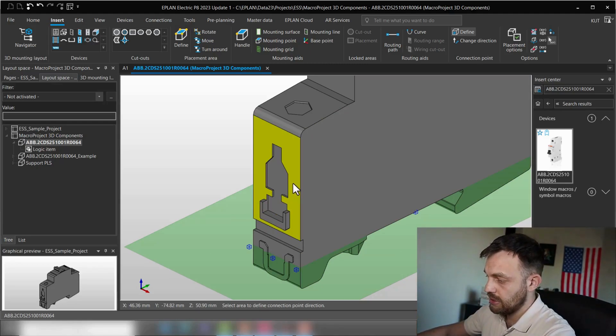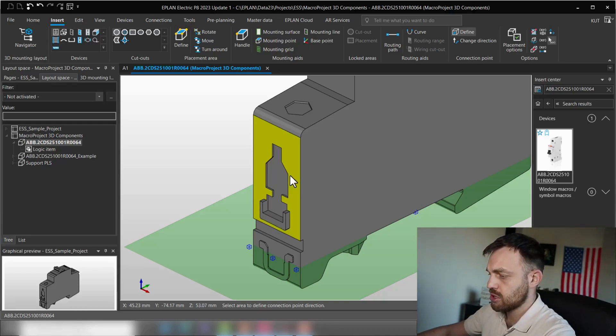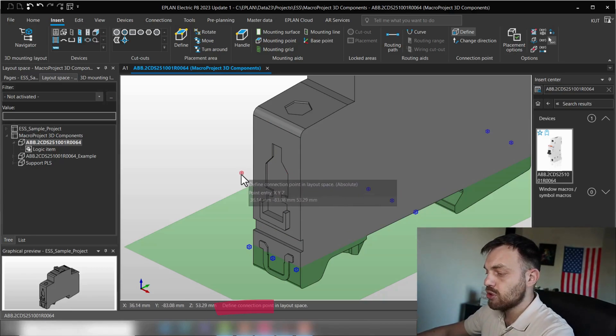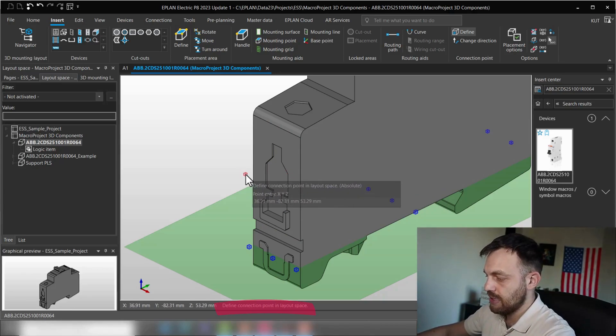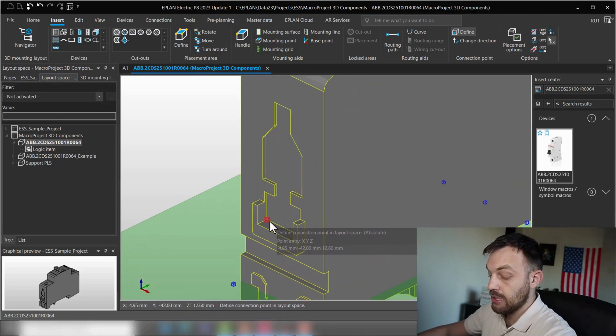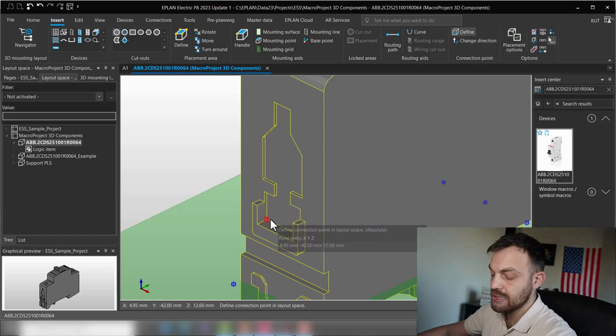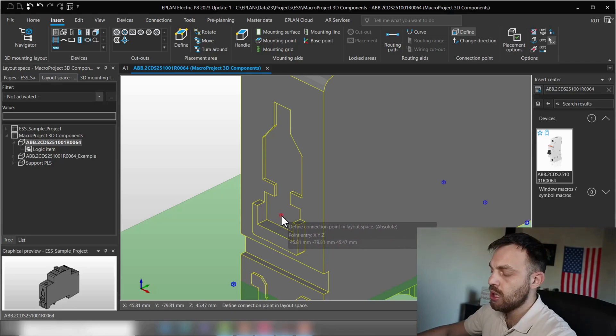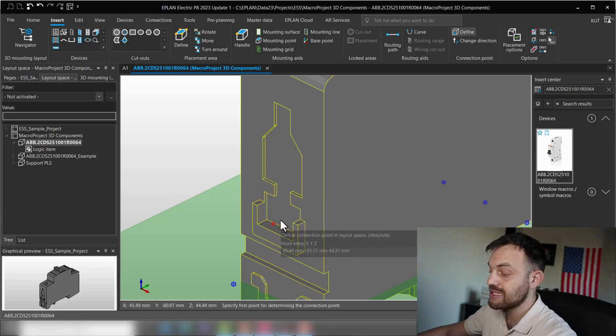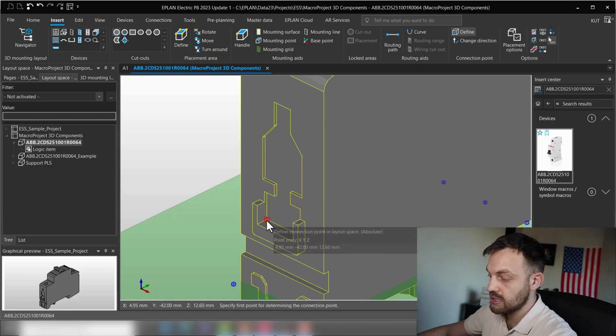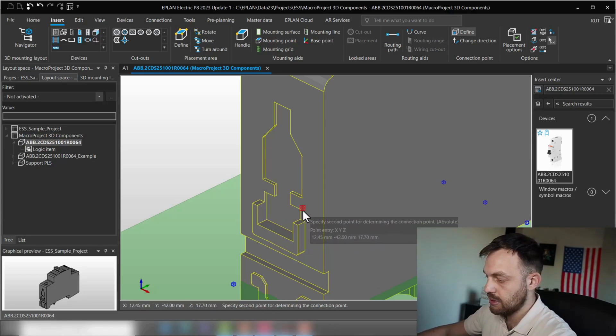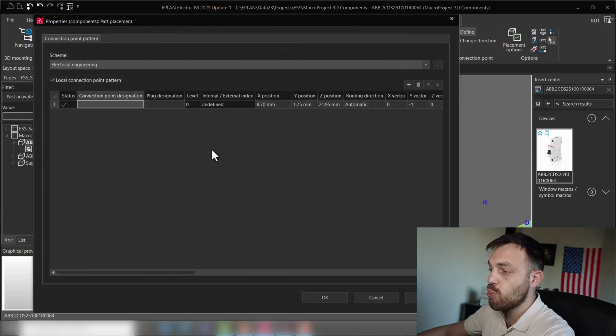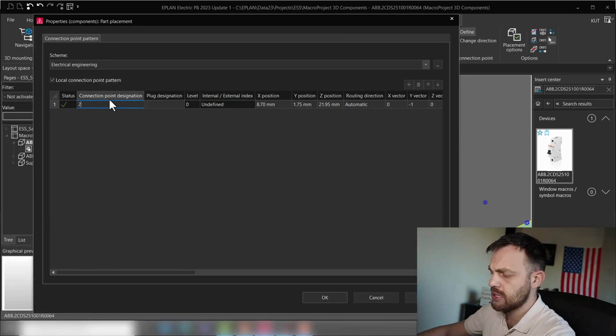So we can either select this surface or this surface for the start. I'm just going to select this. And now, it's time to define the position of the wire termination point. I'll recommend you, if you don't know where it exactly is, or if you can't grab the point which you wish to, but you have edges around it, you can hold control and select those two opposite points. So in this case, control, click here, and click here. This opens this window here, and here we can, for instance, enter connection designation point 2, and press OK.